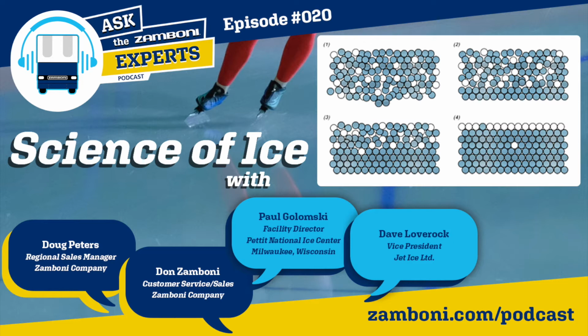Paul, I have a tendency to agree with you on that. But there are a number of rinks out there, like we talk about water treatment. We're not the only water treatment business around, but a number of rinks do run straight RO or DI water. The adding of the mineral content is used in a couple of places. We did it in New York for years. New York has great water. Their water is probably down around 17, 20 parts per million, usually about a grain of hardness.